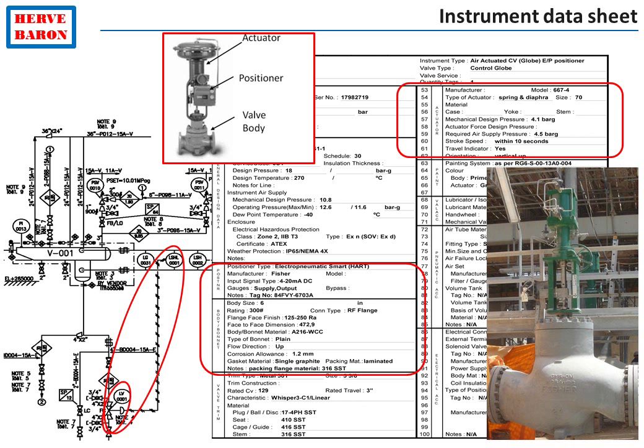The instrument data sheet, also called instrument mechanical data sheet, shows for the body the types of materials to be used for the body and the trim, the type of end connections — this information is specified by piping, so instrumentation gets it from piping. It also specifies the type of actuator, the type of positioner, and the type of signals that will be exchanged between the instrument and the control system.